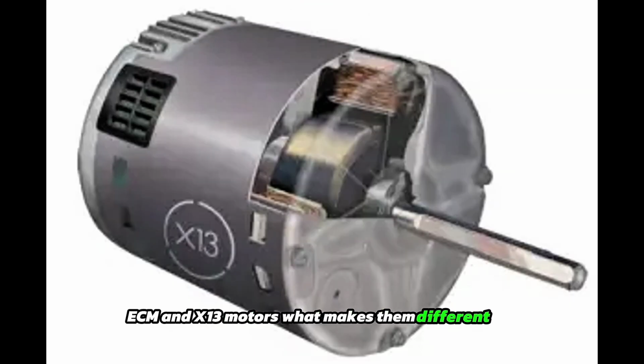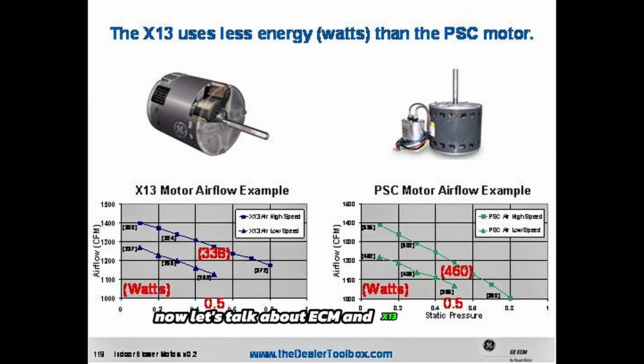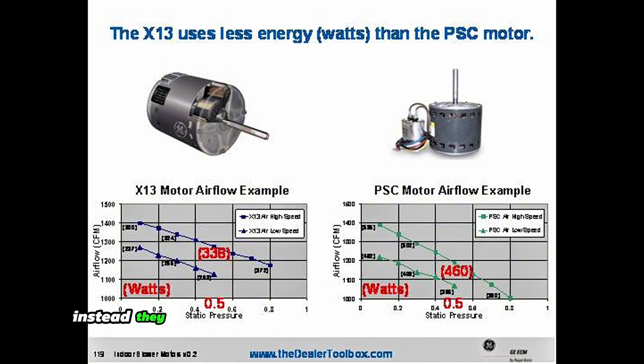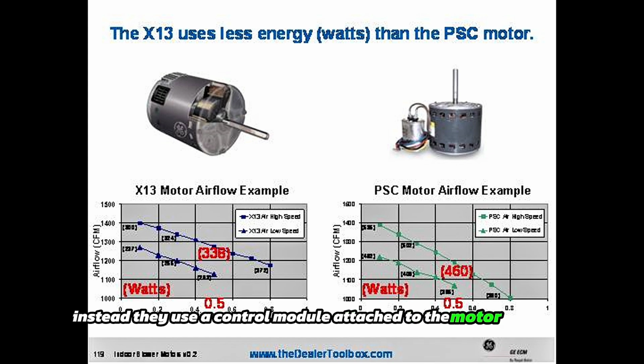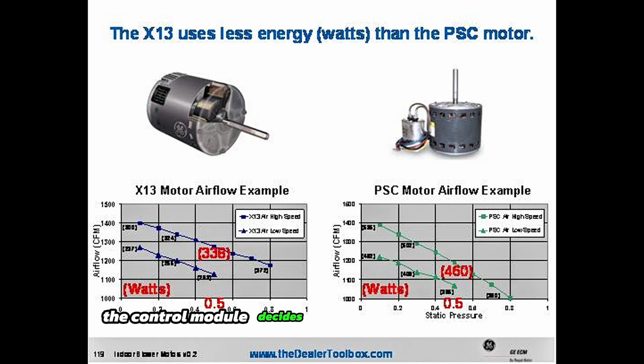ECM and X13 motors. What makes them different? Now let's talk about ECM and X13 motors. These are electronically commutated motors. They don't rely on a capacitor. Instead, they use a control module attached to the motor itself. The control module decides how fast to spin the motor based on signals from the thermostat or control board.